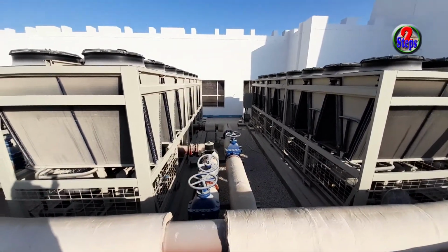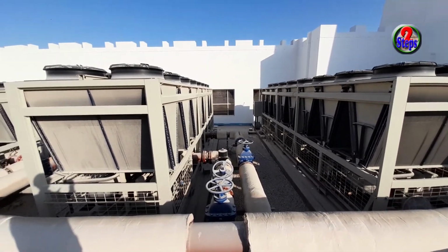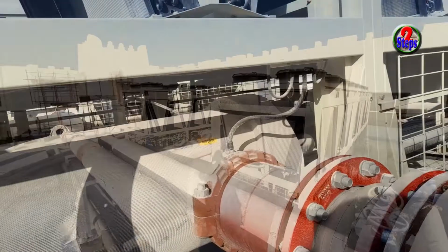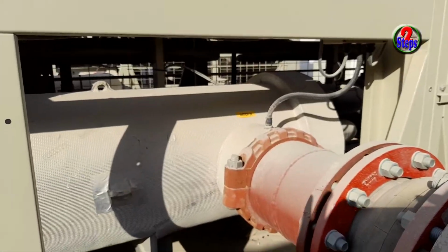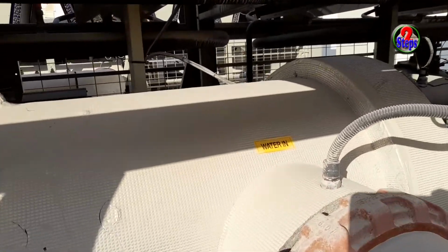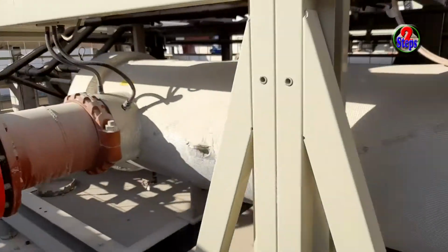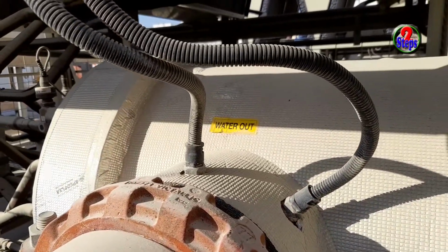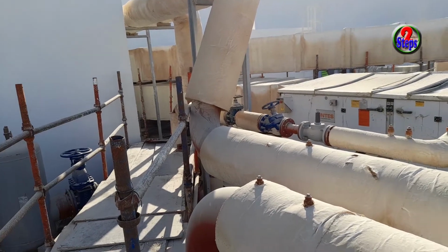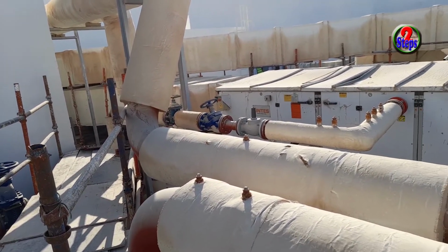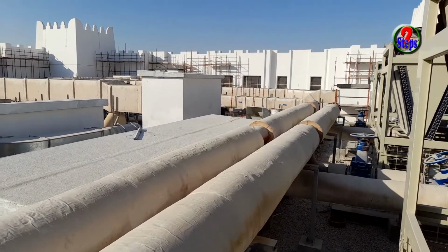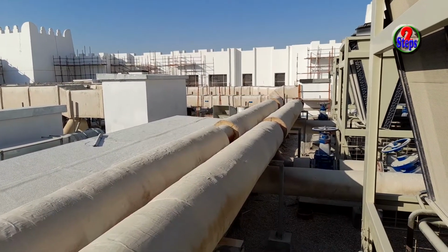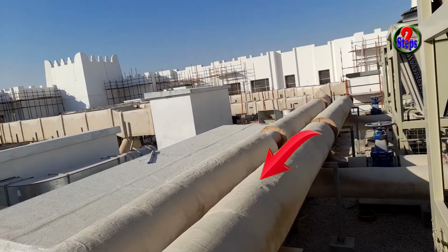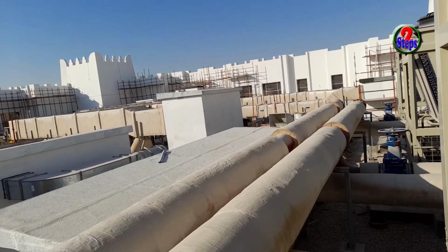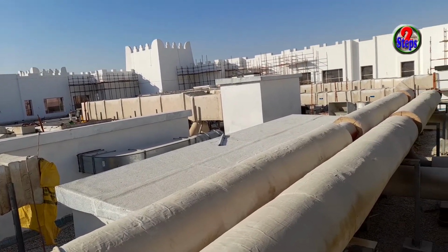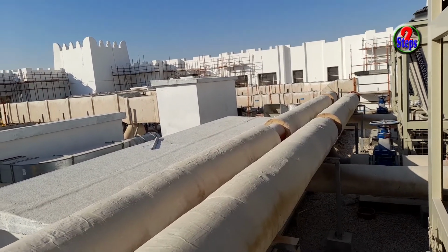Now let's see the connection of this water chiller machine. All the connections are typical. Every chiller unit has 2 connection points. One is water in, that means inlet, and the other connection point is water out, that means outlet. Here you can see 2 main lines. One is coming from primary pumps. It's called chiller inlet header. Other goes to secondary pumps. It's called chiller outlet header. All the chiller inlets are connected to the chiller inlet header and outlets connected to the outlet header.